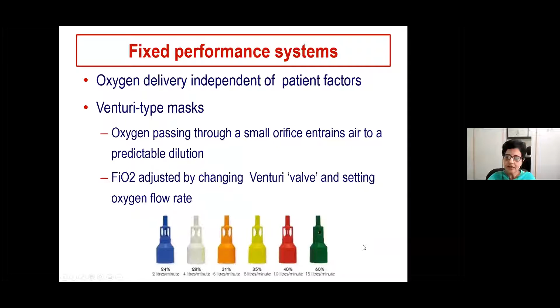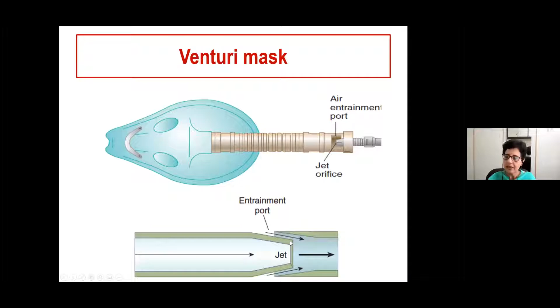So how does it work? There is a mask which is connected to a Venturi device. And like you can see here, this is a cross section of that Venturi device. This is a small orifice through which oxygen is passed. And since it is coming out of a smaller orifice, it is at a higher pressure. Because of this high pressure, there is a drop of pressure alongside this jet, which leads to entrainment of air. So the larger the jet orifice, the less the pressure drop, the less the entrainment, and therefore the higher the FiO2.